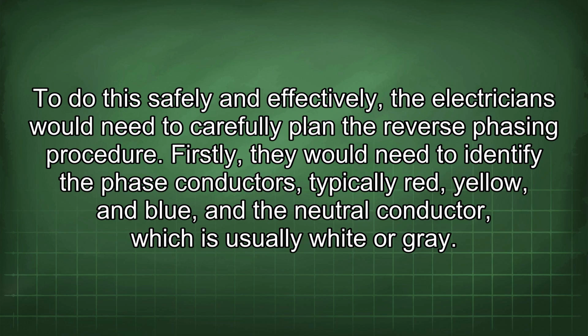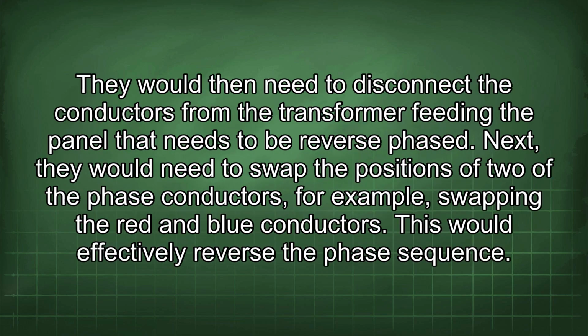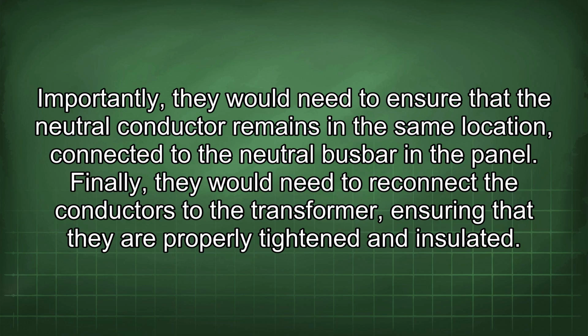Firstly, they would need to identify the phase conductors, typically red, yellow, and blue, and the neutral conductor, which is usually white or grey. They would then need to disconnect the conductors from the transformer feeding the panel that needs to be reverse phased. Next, they would need to swap the positions of two of the phase conductors, for example, swapping the red and blue conductors. This would effectively reverse the phase sequence. Importantly, they would need to ensure that the neutral conductor remains in the same location, connected to the neutral busbar in the panel. Finally, they would need to reconnect the conductors to the transformer, ensuring that they are properly tightened and insulated.